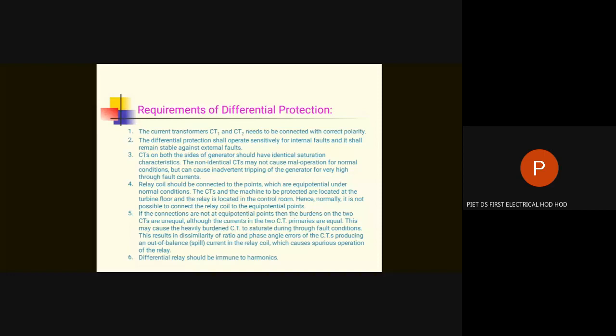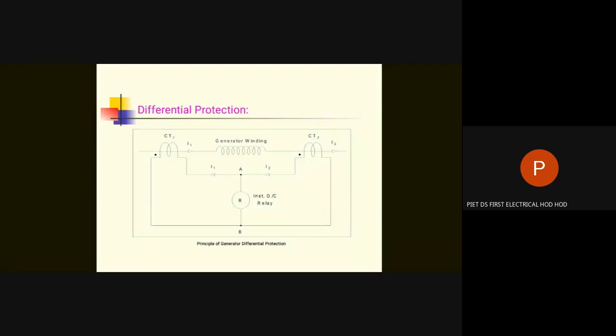The last requirement is that the differential relay should be immune to harmonics. It should not operate for any current other than the fundamental. And harmonics are present if there is an overvoltage surge. So the relay has to be made immune to these overvoltage surges. That means it should be made immune to the surge currents. So what do we do for this differential protection?